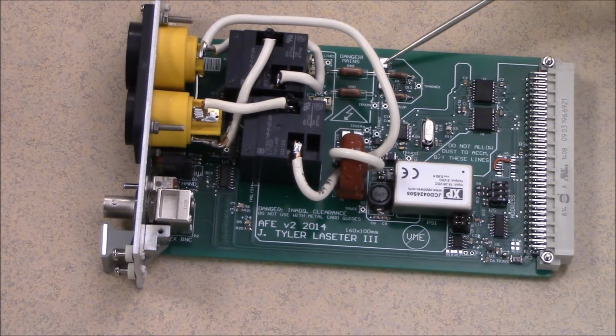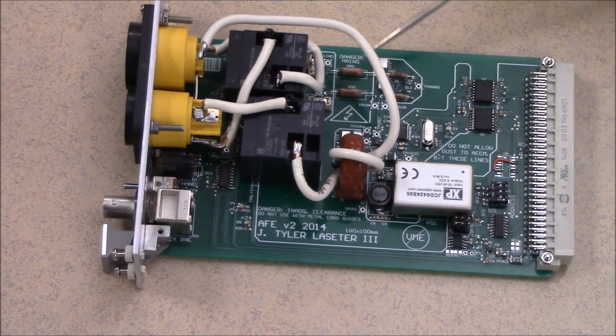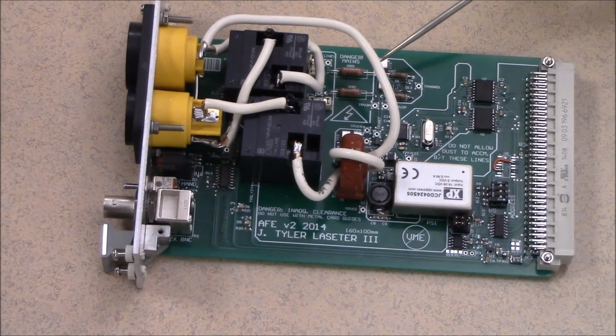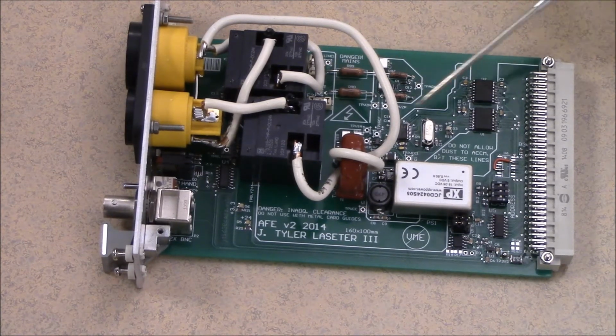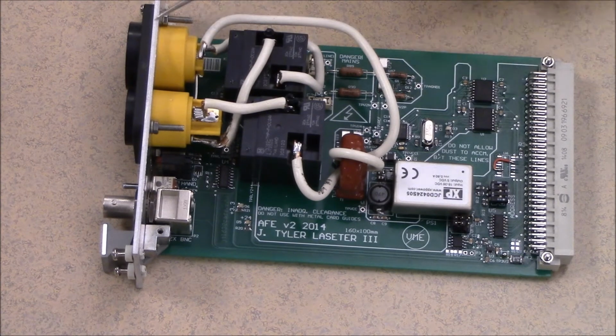Here we have 2 film capacitors that are used for low-pass filtering and 3 bidirectional TVSS diodes that prevent surges from damaging our device. As configured, our device can withstand a 5,000 volt surge without damage. However, that is primarily in terms of the integrity of the measurement circuit and not of our connectors, etc.